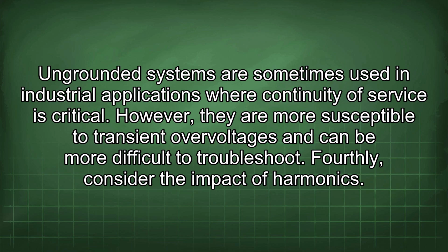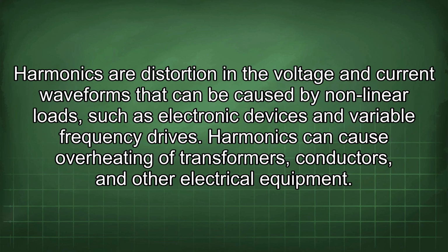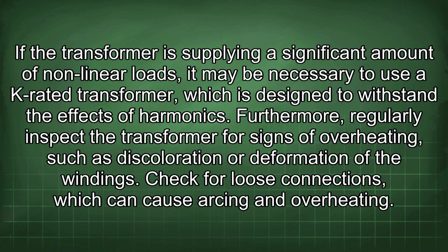Fourthly, consider the impact of harmonics. Harmonics are distortion in the voltage and current waveforms that can be caused by nonlinear loads such as electronic devices and variable frequency drives. Harmonics can cause overheating of transformers, conductors, and other electrical equipment. If the transformer is supplying a significant amount of nonlinear loads, it may be necessary to use a K-rated transformer, which is designed to withstand the effects of harmonics.